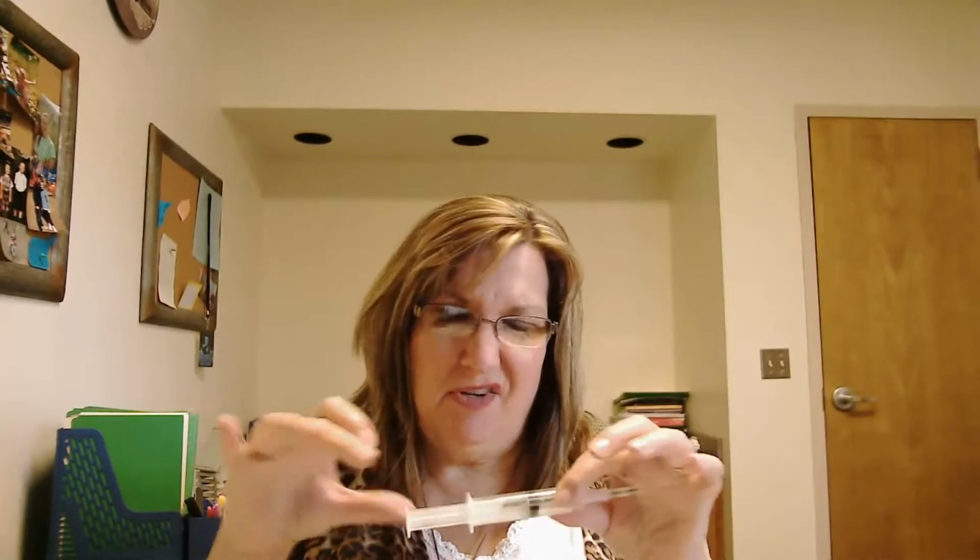Calculate milliliters per hour flow rates for syringe pump. A syringe pump is actually a pump that you could put this on, a different type of IV pump system, and you could put this syringe on and infuse it into your patient. You have to have it set up with proper tubing and everything, but you could do that with a syringe pump. Many syringe pumps may be programmed to deliver medication in flow rates other than milliliters per hour, such as units per minute or micrograms per minute. But that's how they would be programmed. You can use micrograms per minute and stuff like that on syringe pumps.